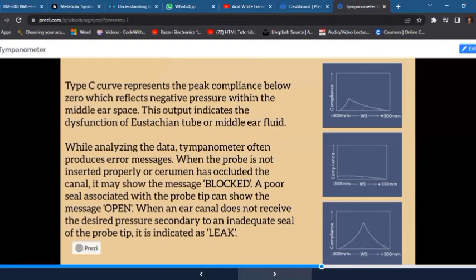While analyzing the data, our tympanometer often produces error messages. When the probe is not inserted properly or cerumen has occluded the canal, it may show the message block or dysfunctional. A poor seal associated with the probe tip can show the message open when it is correctly in the middle ear space. When an ear canal does not receive the desired pressure secondary to an inadequate seal of the probe tip, it is indicated as leak. Now there are the three types A, B, and C of tympanogram on the right of the slide.